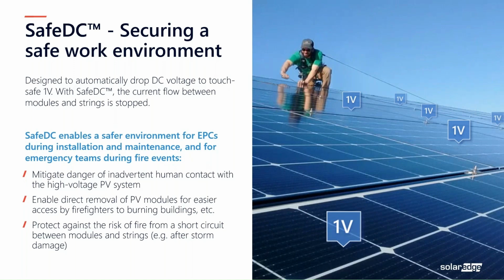So if there was an incident where the fire alarm was not in fault mode but operational mode, the firefighter panel, or the fire alarm panel, would link directly to the One Controller. The One Controller links to the PV inverters, and within a matter of seconds the signal will be sent to shut down. There is comfort for the fire rescue service going in, knowing that if they were to go onto the roof, there would be no additional hazards such as electricity or electrocution, and they didn't have to worry about the PV system being live.